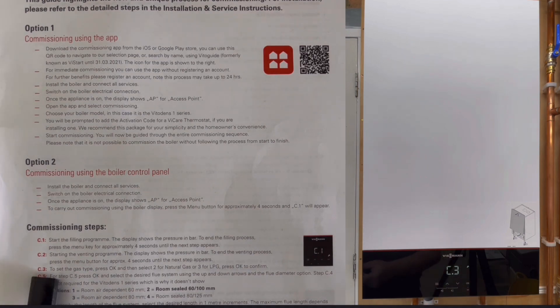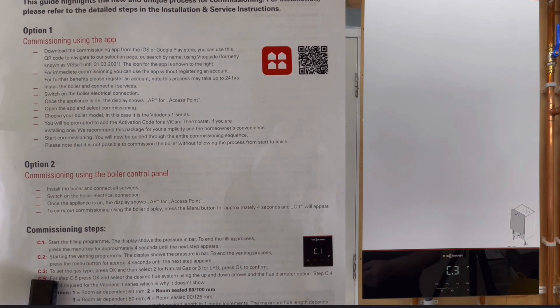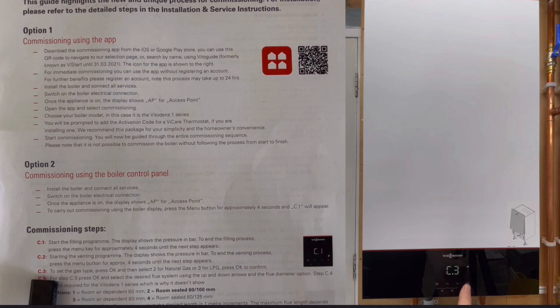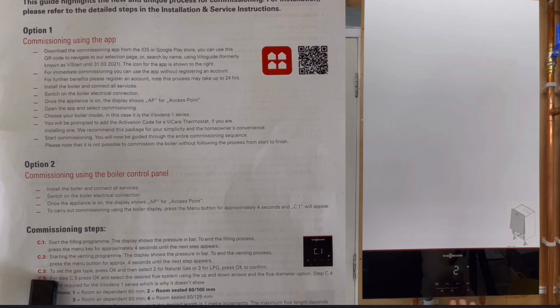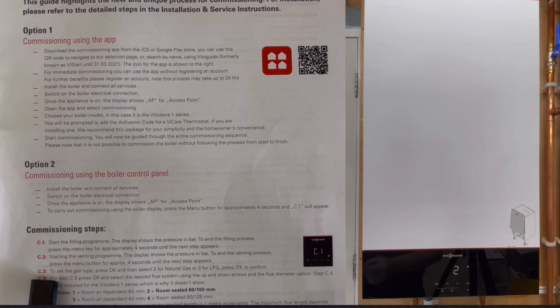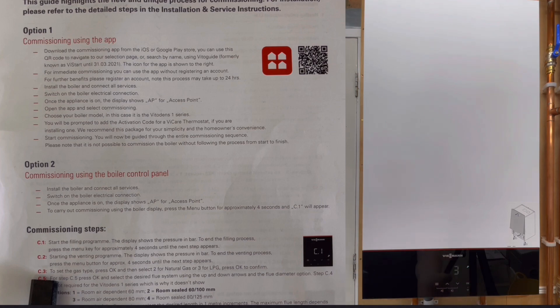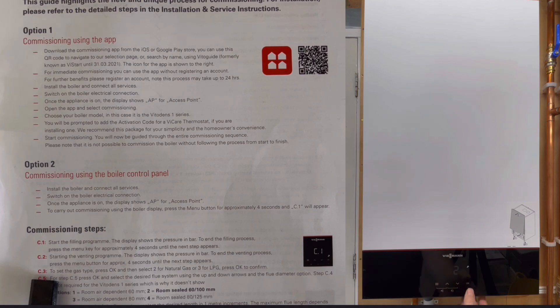Then it takes us to C3. C3 is to set the gas type. If we had this on LPG then we might want to change it, or natural gas depending on which one we wanted it on. We click on OK and we've got a number two in there. Number two tells us it's for natural gas. If we did click on that we could change it to three and three would be LPG, and then we would click OK if we were going to put it onto LPG. On this video we're going to put it onto number two which is natural gas.